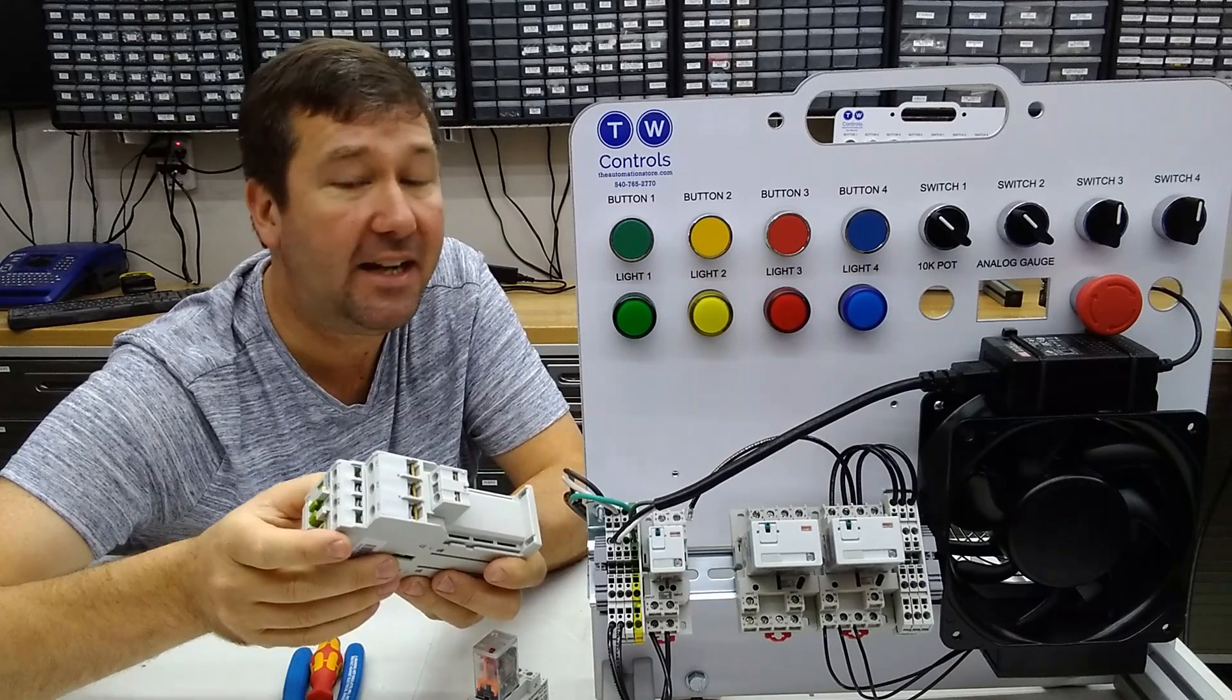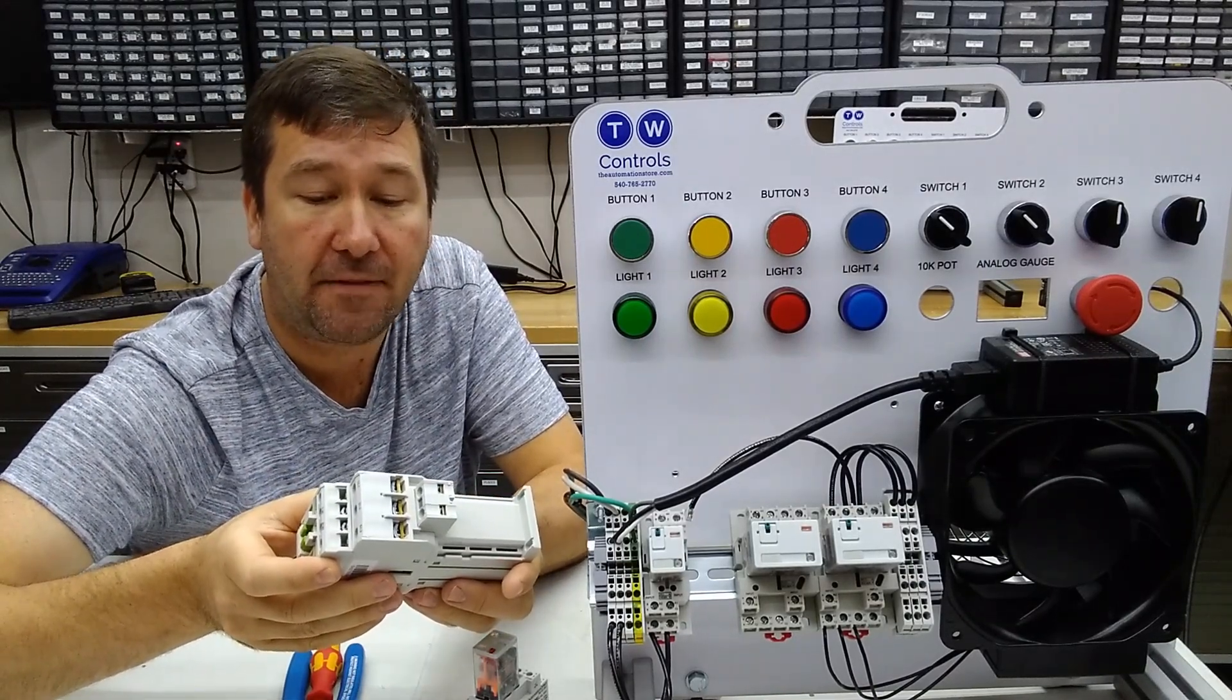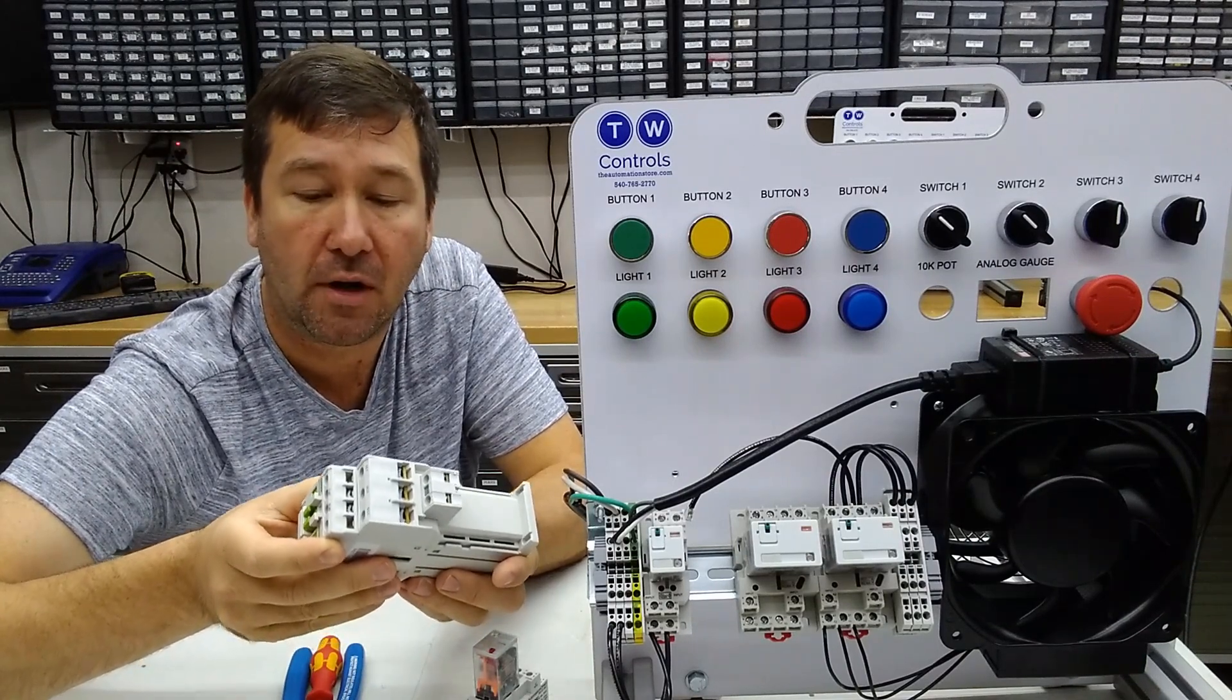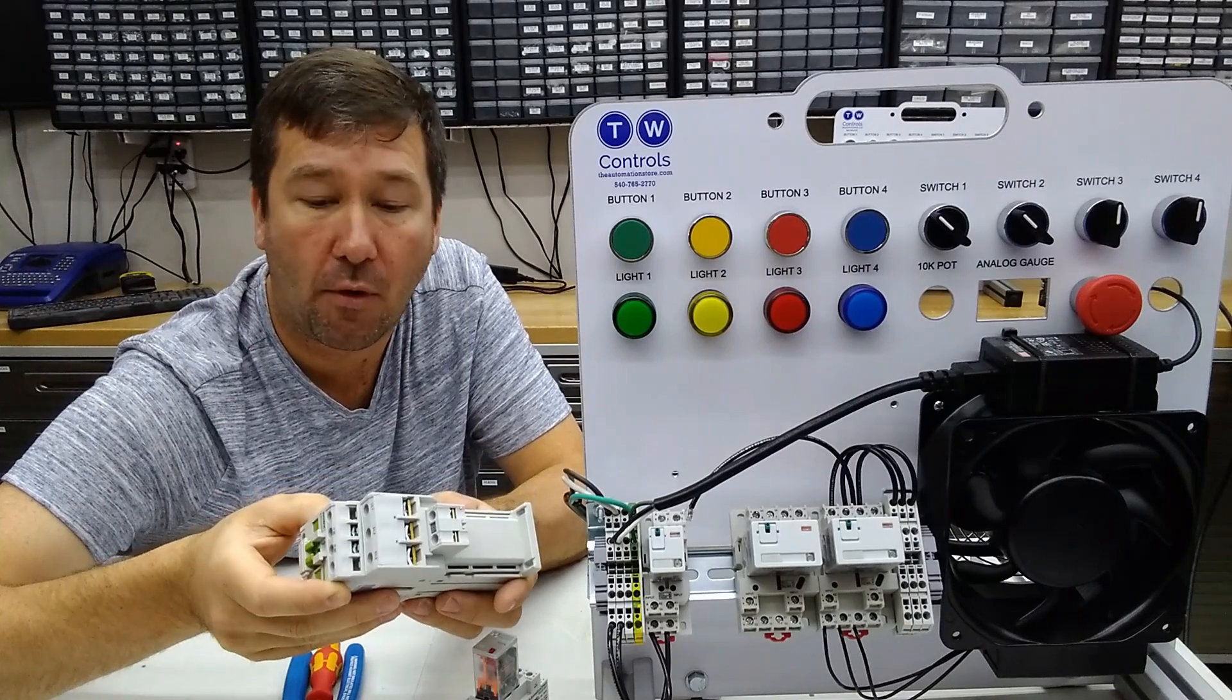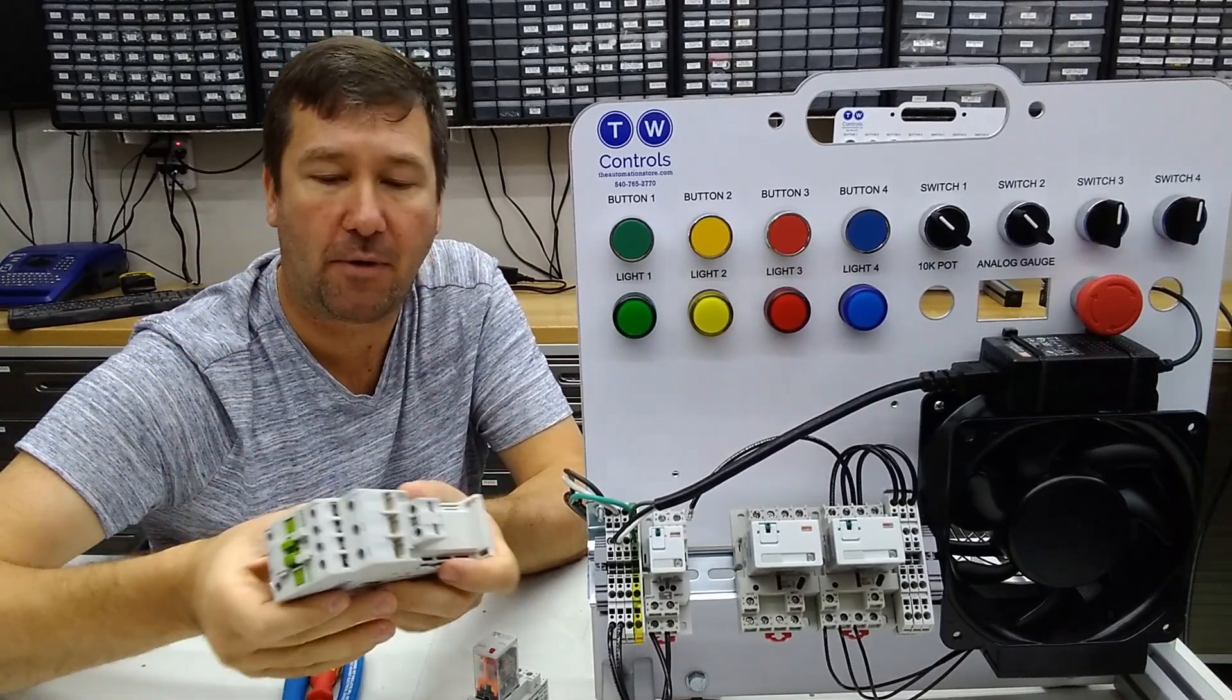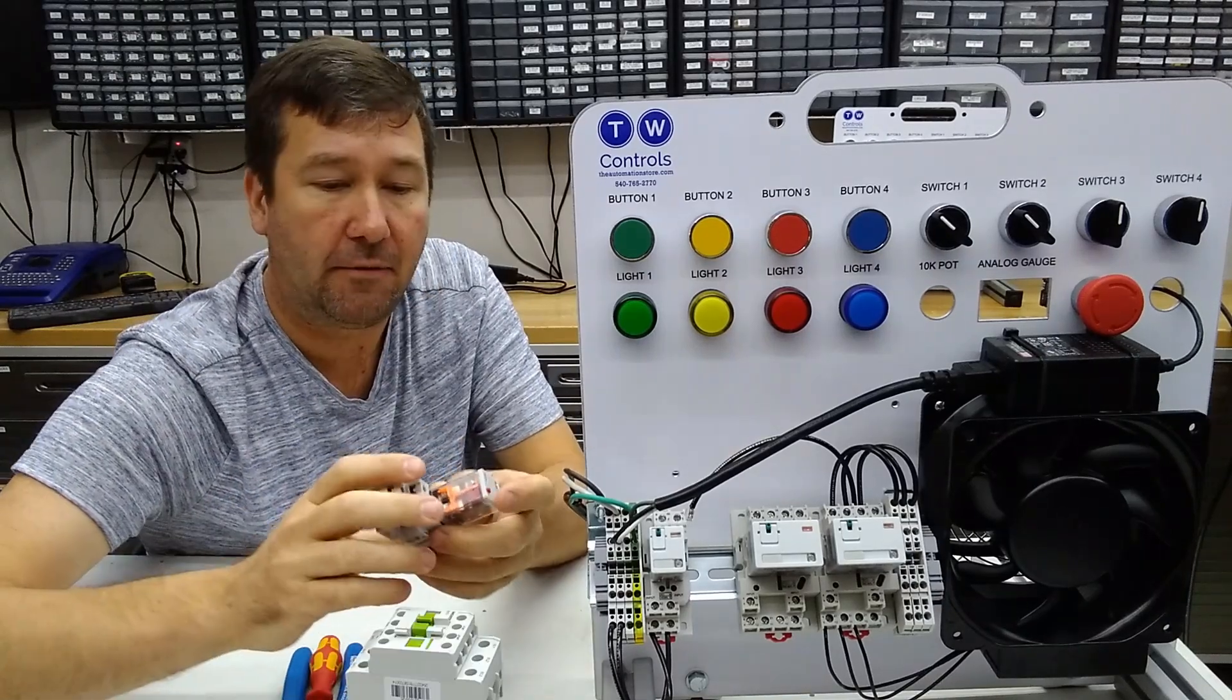Then it has three phase ratings. And so at three phase, this one can handle seven and a half horsepower at 240 volt, or it can handle 15 horsepower at 480 volt. So as your voltage goes up, typically your horsepower rating will go up also, up to a limit.